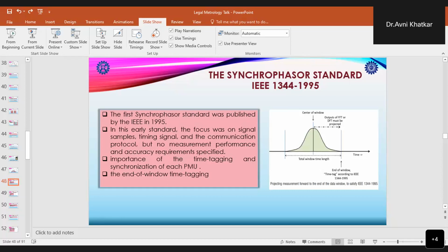And this end-of-window time tagging brings a lot of problems, like the projection process made the measurements much more susceptible to sampling noise and any imperfect power quality. Also, quite different results were seen from different brands of PMUs, or even some identical PMUs, which were not showing the same results because they were using different algorithms or different window lengths or window shapes, maybe during their dynamic events. So such problems were associated with this standard.